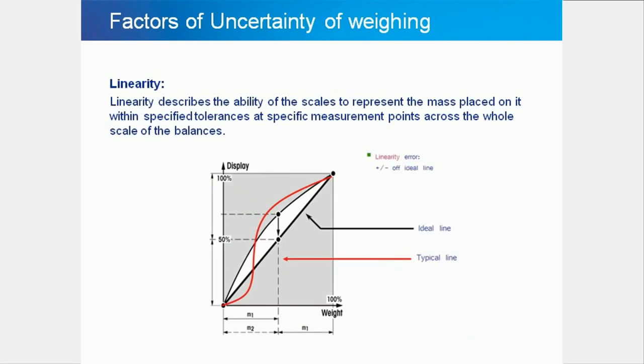Linearity describes the ability of the scales to represent the mass placed on it within specified tolerances at specific measurement points across the whole scale of the balances.